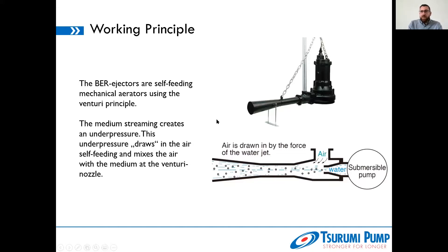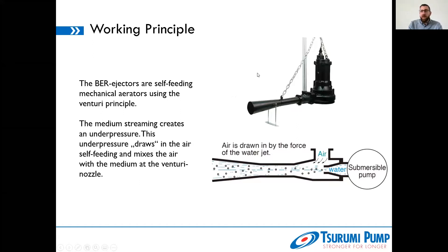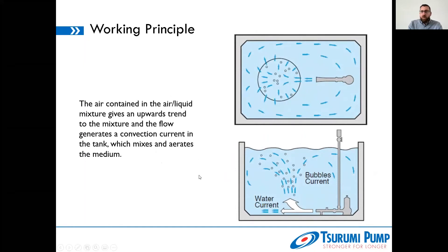As you can already see here, the main difference compared to the TRN aerators is that we just have one aeration direction. We are not talking about a radial system anymore. We are talking about a system with a defined streaming that you can already see in the trumpet in front of the machine. This is exactly the direction that the mixture of water and air leaves the machine, creating both the aeration effect and the streaming. The working principle results in a bubble pattern that the machine creates in the tank.